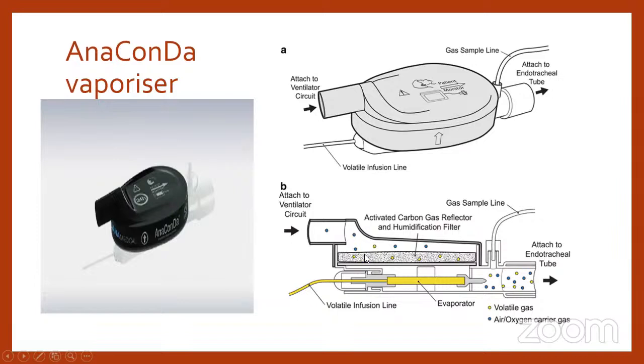So when it is incorporated into the circuit, the fresh gas comes to this place, and this is another line for the volatile infusion line. This is basically the anesthesia agent line. So the liquid anesthetic comes into this chamber. There will be an evaporator inside the Anaconda vaporizer, so it gets vaporized here and is incorporated into the fresh gas that is flowing in the upper circuit.